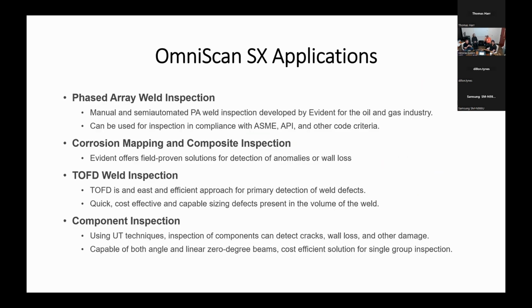So some of the applications that the SX is good for, as far as weld inspection is concerned, so manual and semi-automated PA weld inspection has been developed by Evident for the oil and gas industry. It can be used for inspection that's in compliance with ASME, API, and other code criteria, AWS D1.1 is another one. It can be used for corrosion mapping and composite inspection. So we do have field-proven solutions for detection of anomalies of wall loss. TOFD weld inspection. So TOFD is an easy and efficient approach for primary detection of weld defects. It's quick, it's cost-effective, and it's capable of sizing defects present within the volume of the weld.